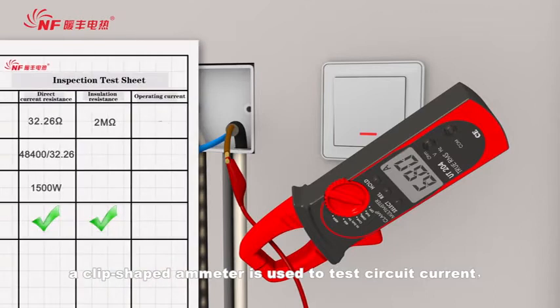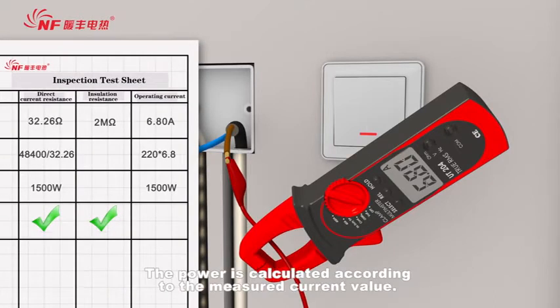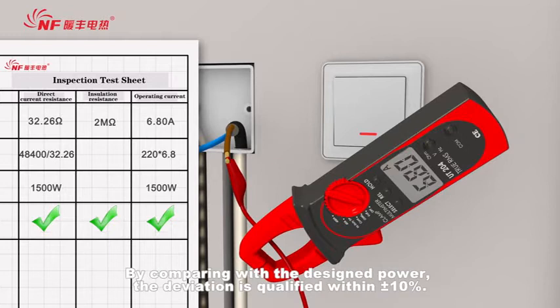A clamp-type ammeter is used to test the circuit current. The power is calculated according to the measured current value. By comparing with the designed power, the deviation is qualified within plus or minus 10%.